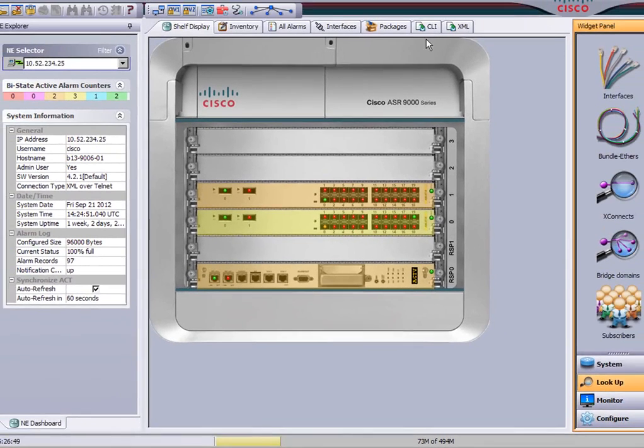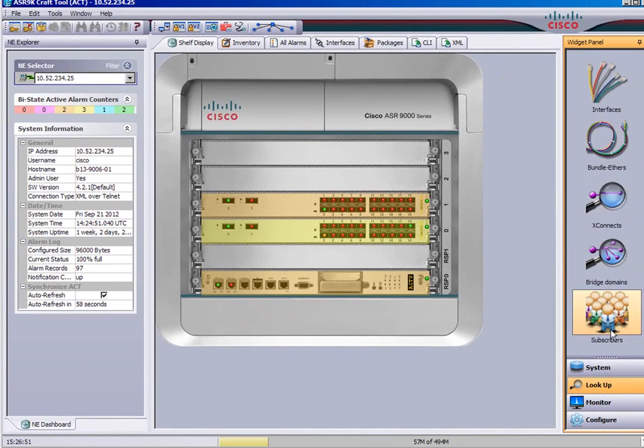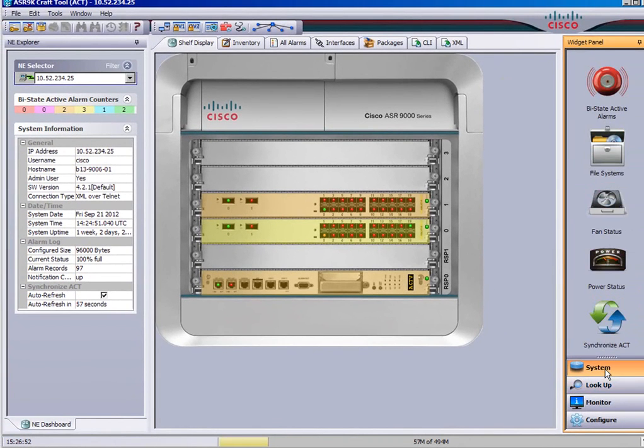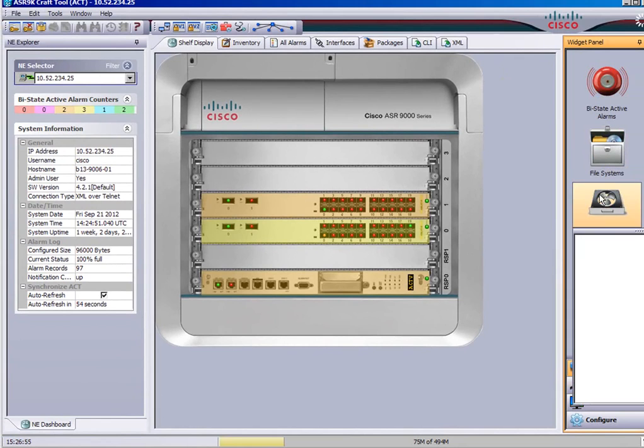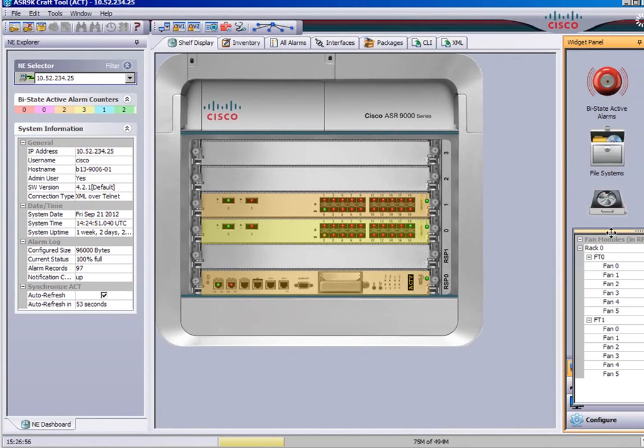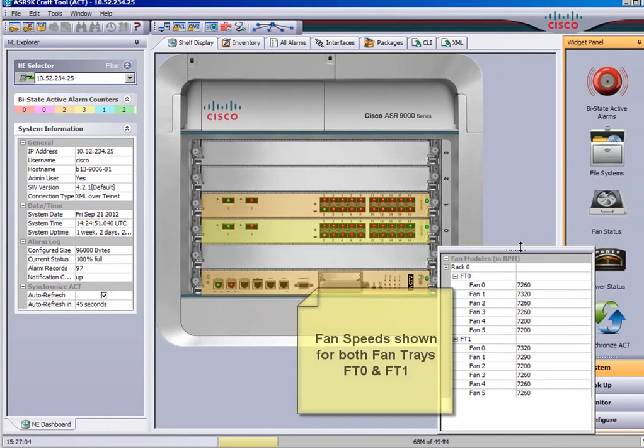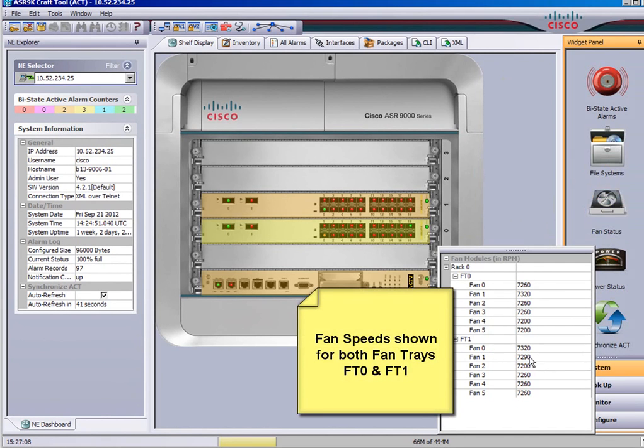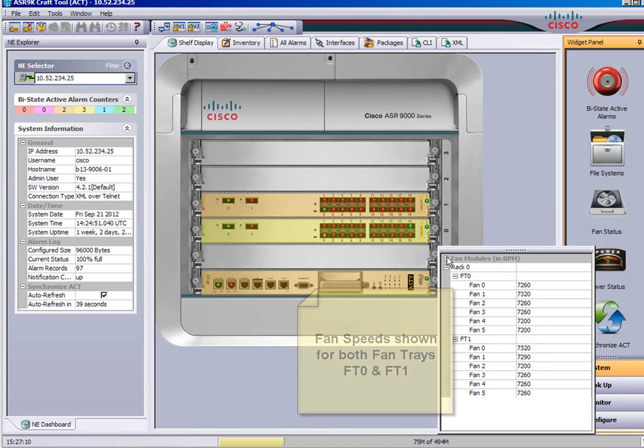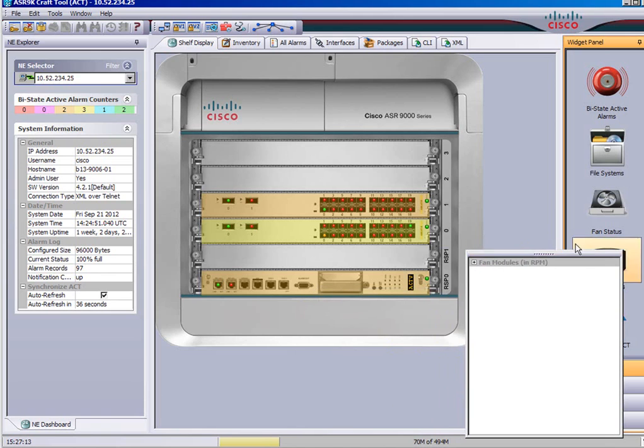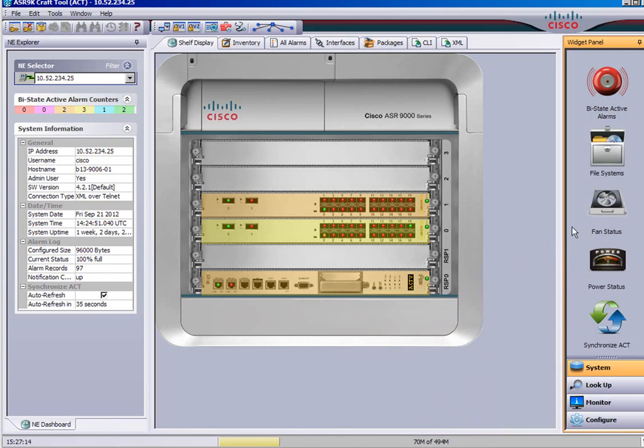Another widget, fans and power supply status. So you can click on the fans and it shows you the RPM of the fans. Two fan trays and they should be running about 7200 and something revolutions per minute. Obviously if the fan slows down or stops you'll see it there.